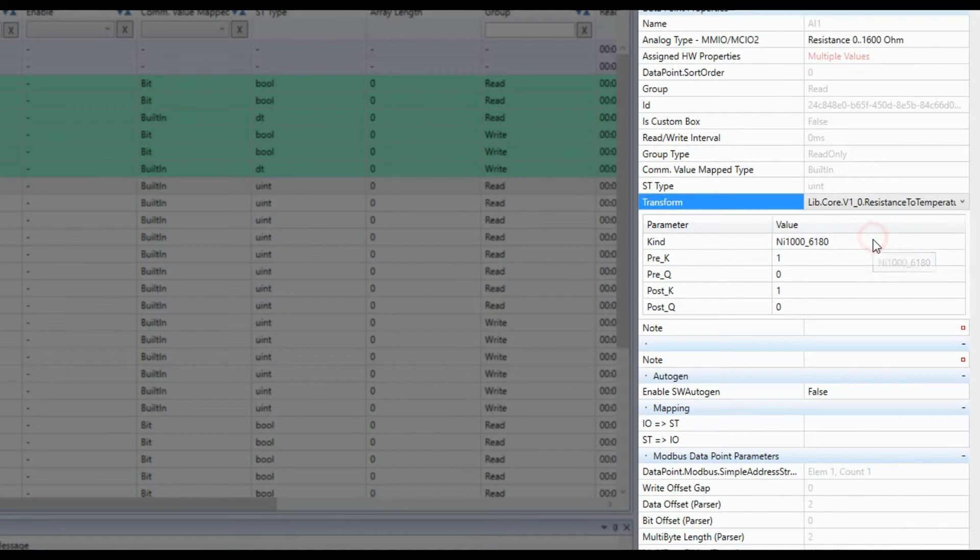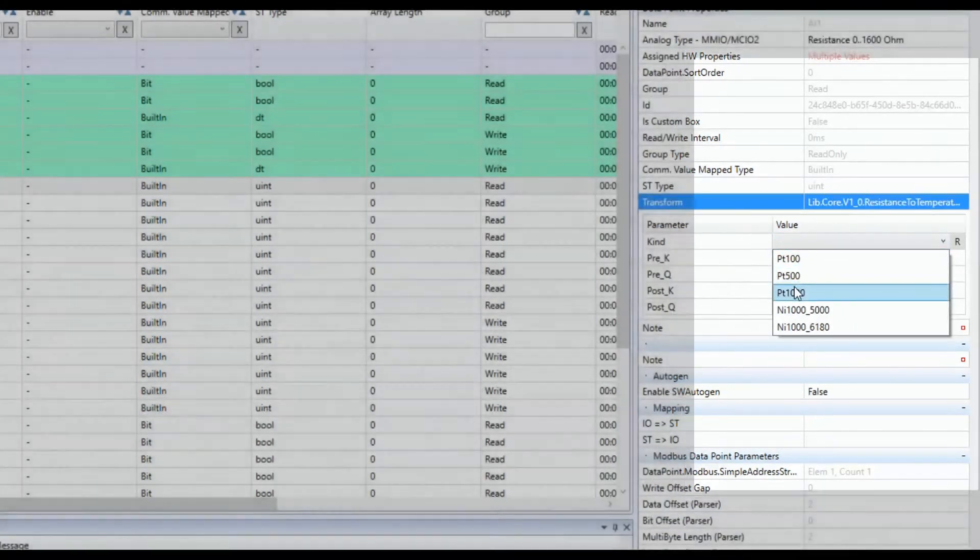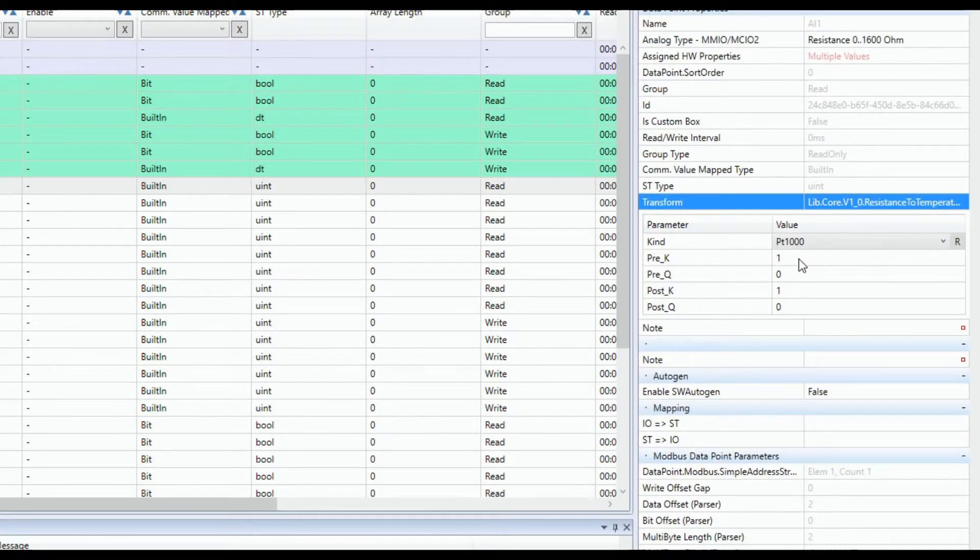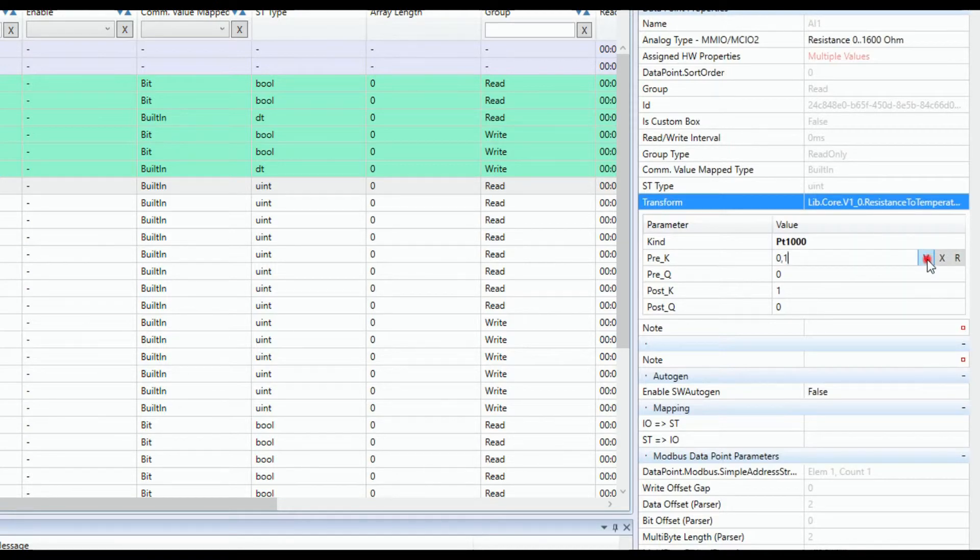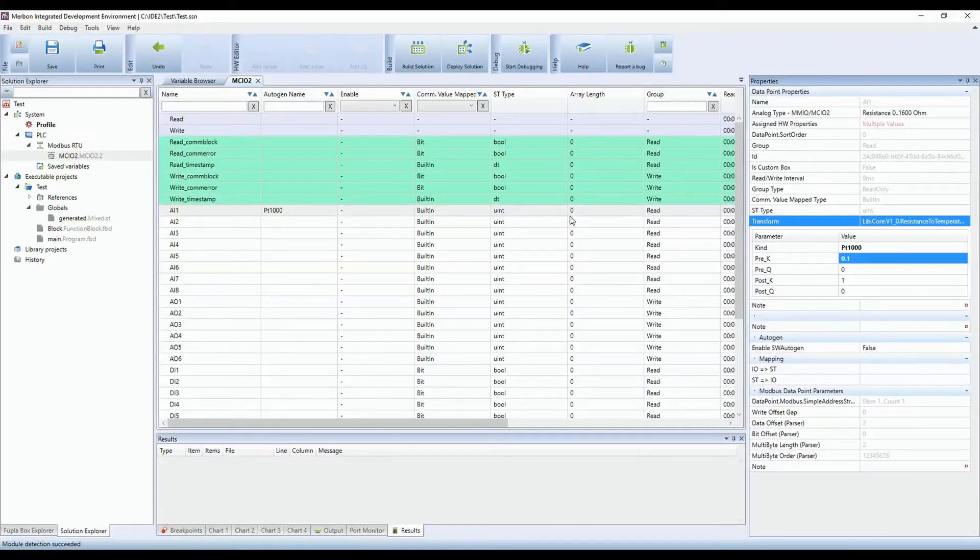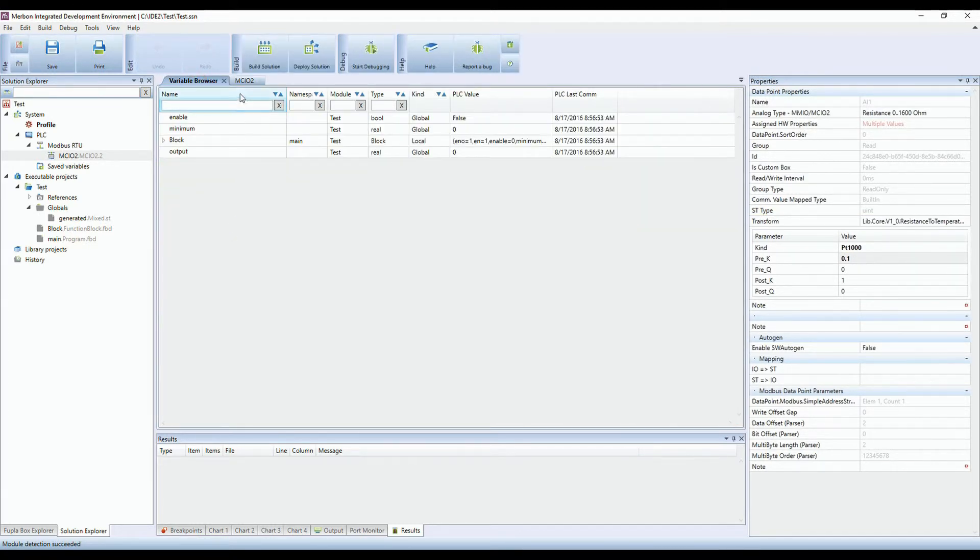You then have to select transformation to transform the resistance to temperature. Choose sensor type PT1000 and change the pre-K parameter to 0.1. Resistance 0 to 1600 ohm is measured on range 0 to 16000 points. Therefore, we need to shift the decimal point to left.